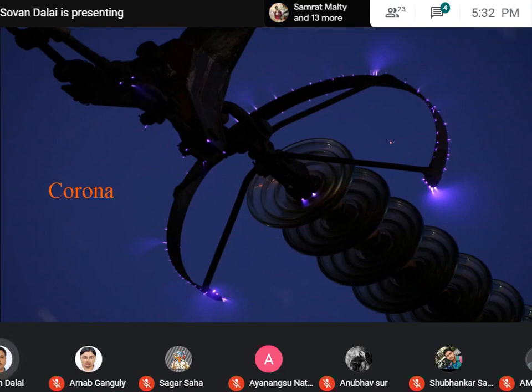What is the phenomenon? You are seeing that in certain portions some violet glow light is coming from different portions of this insulator as well as from this metal structure. So what is this violet glow? The surrounding air ionizes, and if the ionization is more, it produces visible light. That is called corona, and corona does not require two conductors. This is not a breakdown between two conductors. When we are supplying power through a conductor at very high voltage, in the range of 132 to 220 kV, this phenomenon is governed not only by the voltage level but by the electric field intensity.